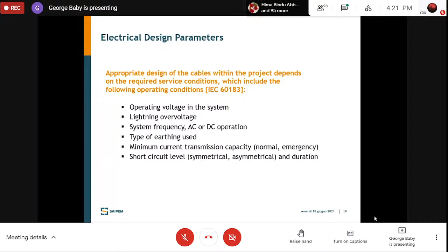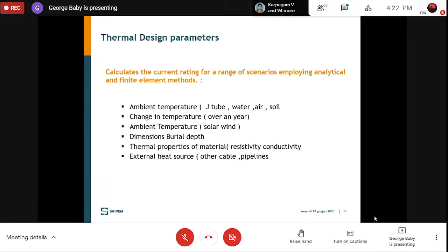The other driving factor which decides the design parameters of a subsea power cable is the thermal design rating, which I have explained to you before. The ambient temperature, the change in temperature over the year, in places like Russia and Kazakhstan the temperature goes from 50 degrees to minus 15 to 20 degrees. So the cable shall be designed accordingly. Then the dimension of the reel, which I will come to later, then the thermal properties of the cable, the material, then the external heat factors.